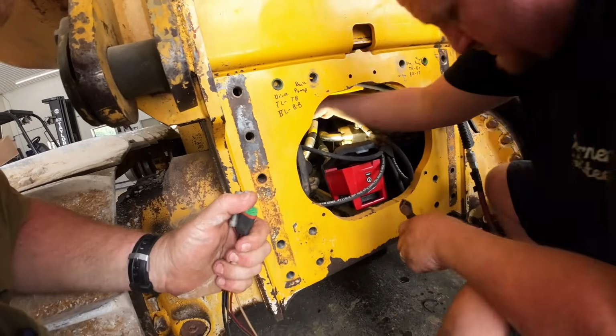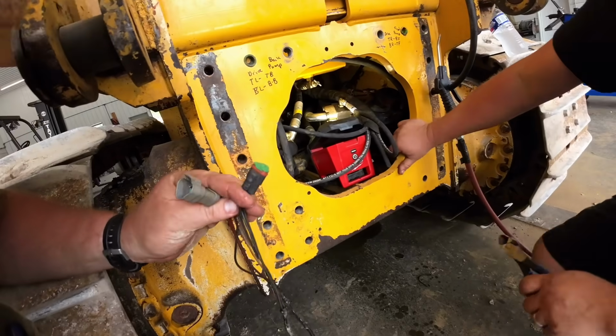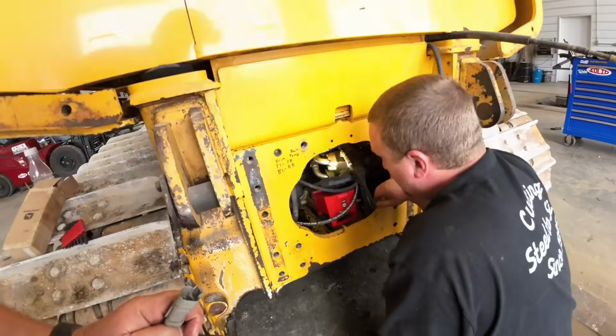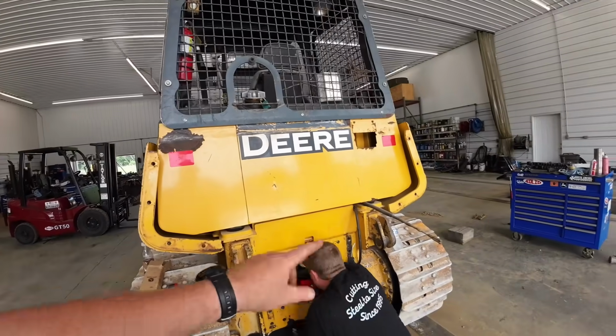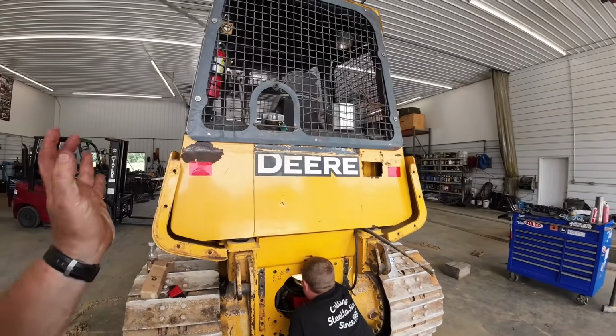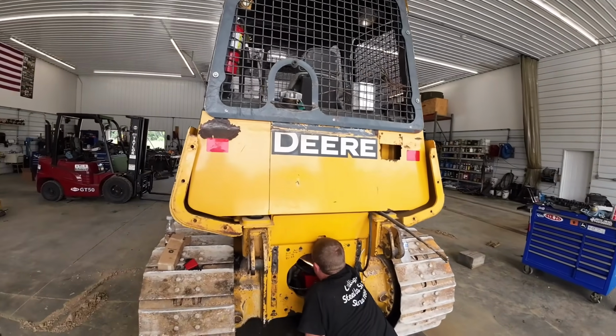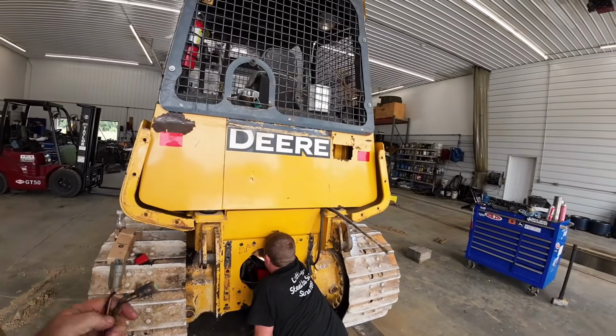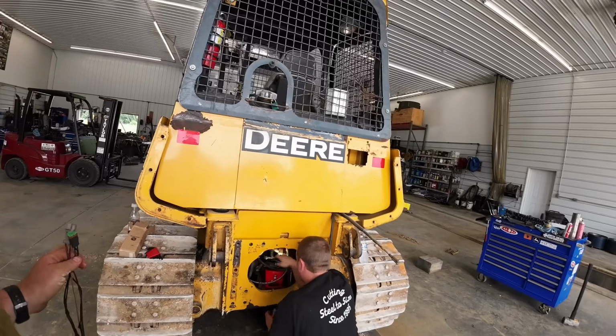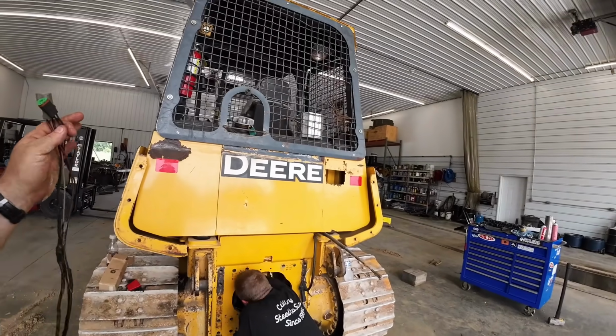So what we're going to do, I've got this jumper made up here. We're going to swap the speed sensors from left to right, switch them around, see if the problem goes to the other side. If it does, that tells me it's probably that speed sensor. But usually if those things are reading RPMs up there, it's good.